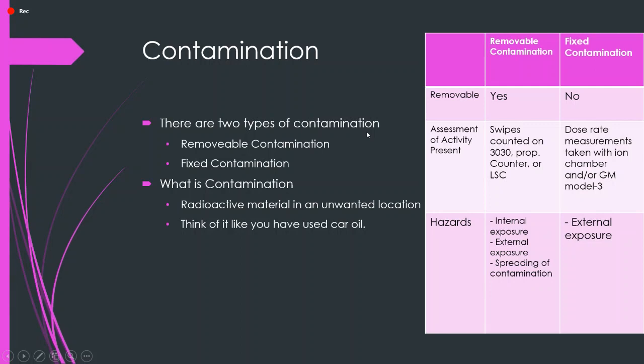The other kind of contamination, of course, is fixed contamination. The way we deal with fixed contamination, it's non-removable, right? The way we can measure it and see how much of it is there is by dose rate measurements. We take ion chambers, we make sure we see how much there is, Geiger-Müller tubes, and we assess how much external exposure you're going to get from that contamination. It is always going to be in that area. There's no ability to decrease it, but at the same time, you stay at equal risk with it at all times.